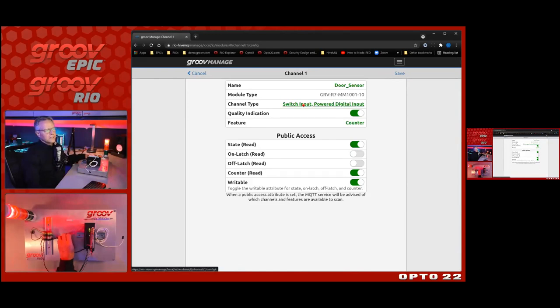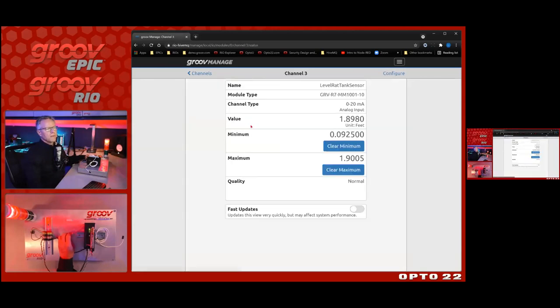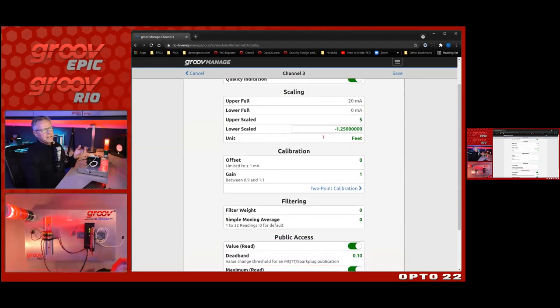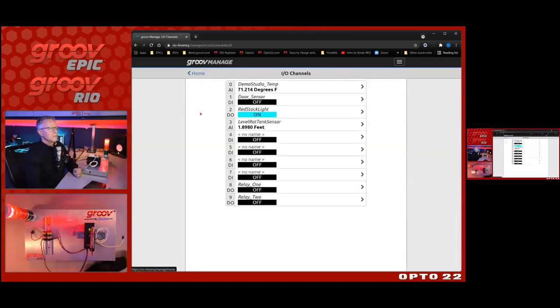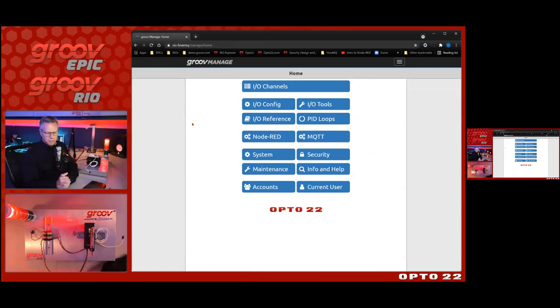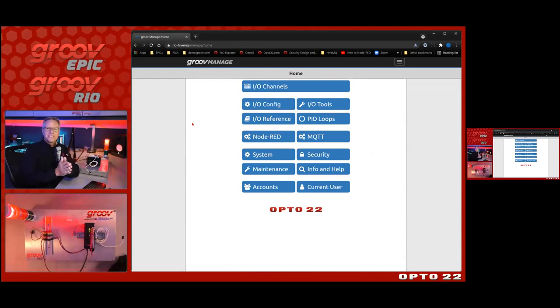For the 4-20 milliamp level transmitter I choose the signal type and set a dead band to avoid publishing jitter from the sensor, reducing message count while still providing meaningful data. That covers sensor configuration. On the EPIC behind me, we're already connected to the PLCs and pulling data in. The next step is configuring where to send the data — MQTT is the way to go — and one challenge in the industrial arena is: what's a broker, how do I get one installed, and on what server?